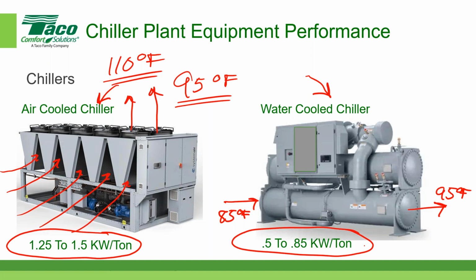Well, I think I've seen the packaged air-cooled chillers are in the order of magnitude of around 300 tons. Now, you can probably have a custom-built air-cooled chiller that's larger than that, but 300 tons is about the average for a packaged air-cooled chiller. That's about as large as they get. On water-cooled chillers, they can go significantly larger. There are some projects that we've looked at recently that are over 2,000 tons per chiller. So there's a huge difference in terms of potential capacity.